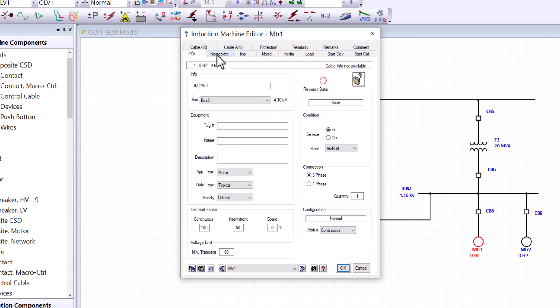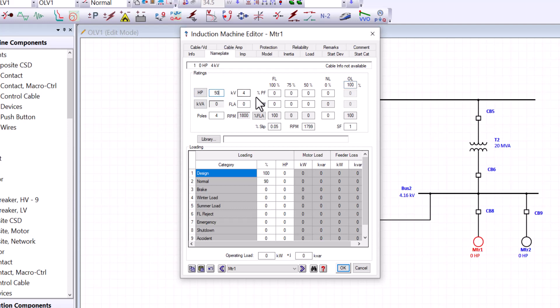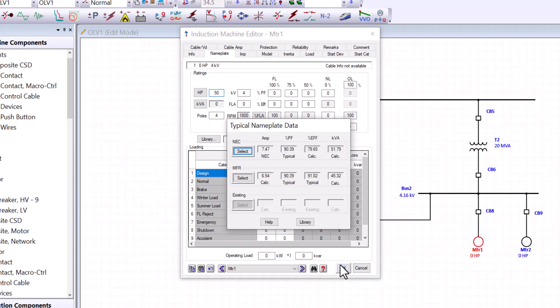Next, I want to talk about the nameplate. In the nameplate, we can assign a horsepower value. And in our case, this is going to be a 50 horsepower, 4kV. And in here, we are looking for some important data such as the power factors and efficiency associated with this motor. You can use some typical values. And I will do that by pressing OK. And that would bring me to this typical nameplate data. We can select the typical nameplate data from the NEMA for a 50 horsepower motor.